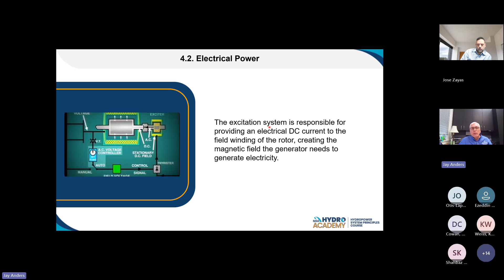Hydro plants are really cool, and I wish I had more time to talk about synchronous converters and synchronous condensing, but it gets to a way that we can actually have minimal watts on our units and basically running them as a motor, and I can supply a lot of VARs to the system. You might hear it as VAR control, getting that voltage stability. It's one thing that really causes a lot of issues on the grid is voltage control. And so that's what my excitation system allows me to do.